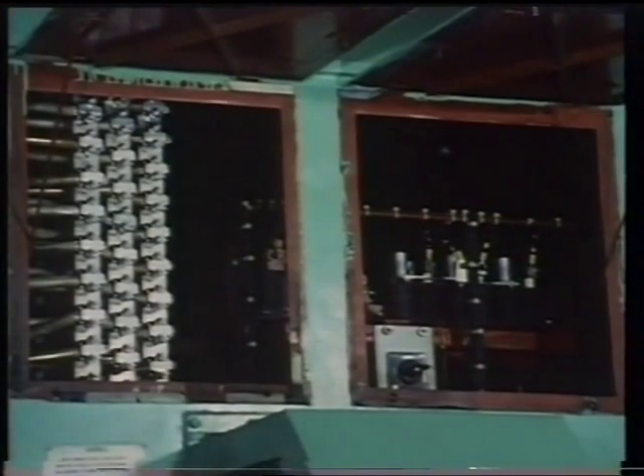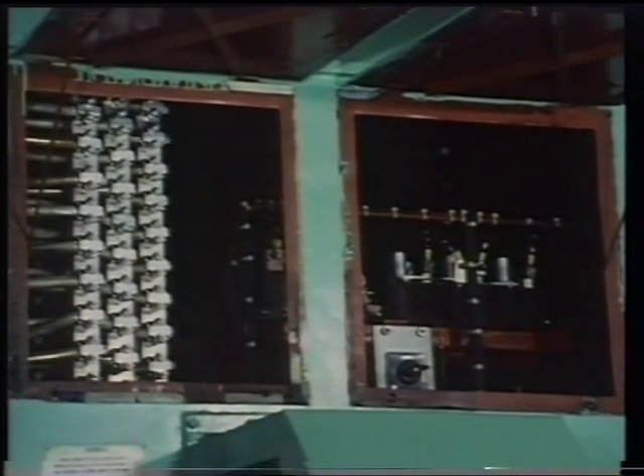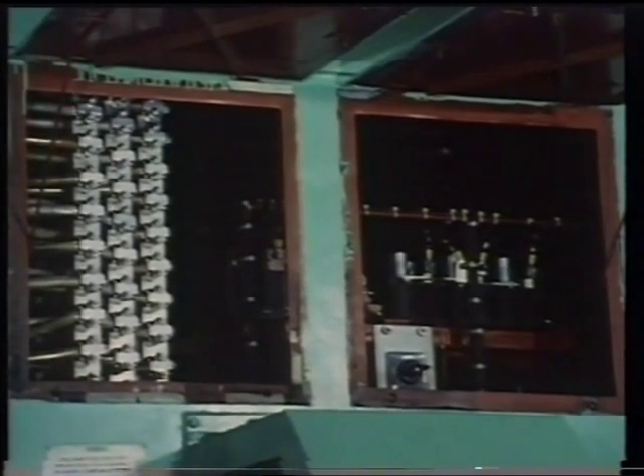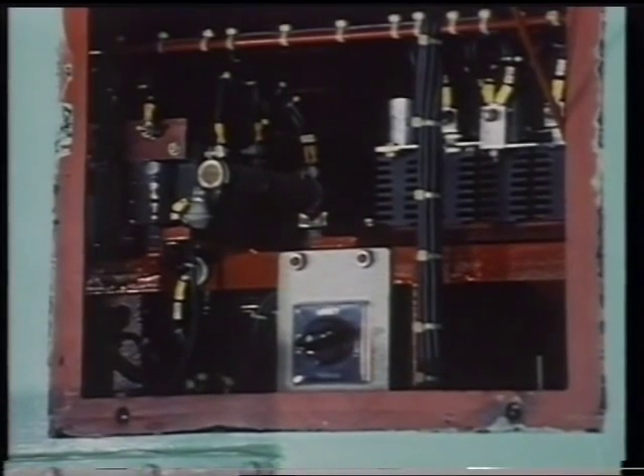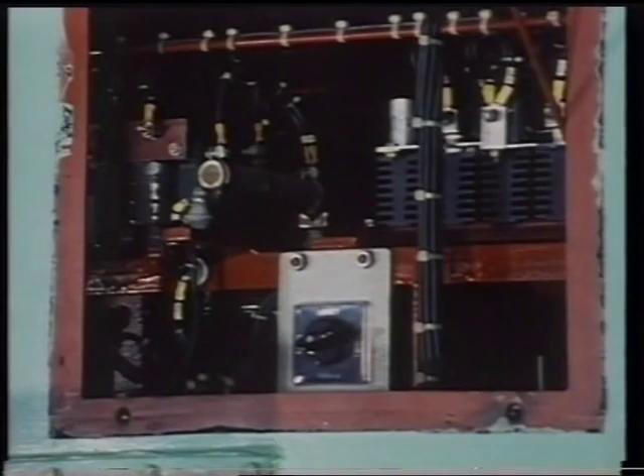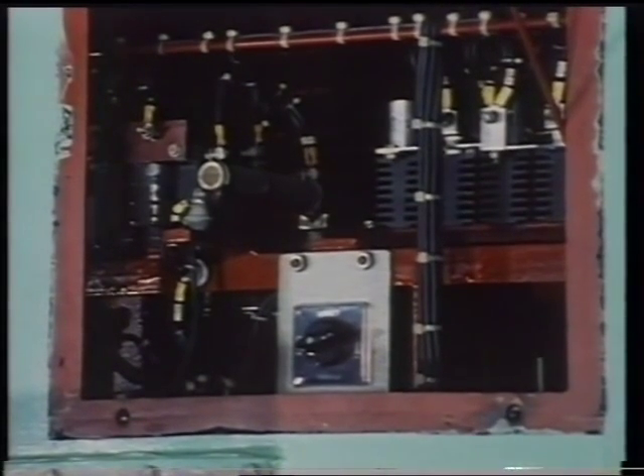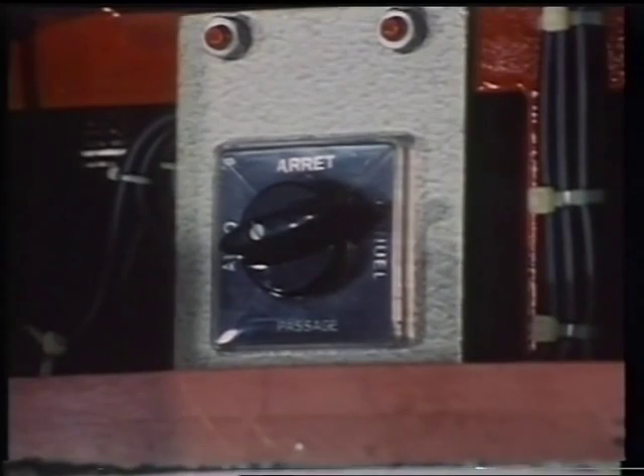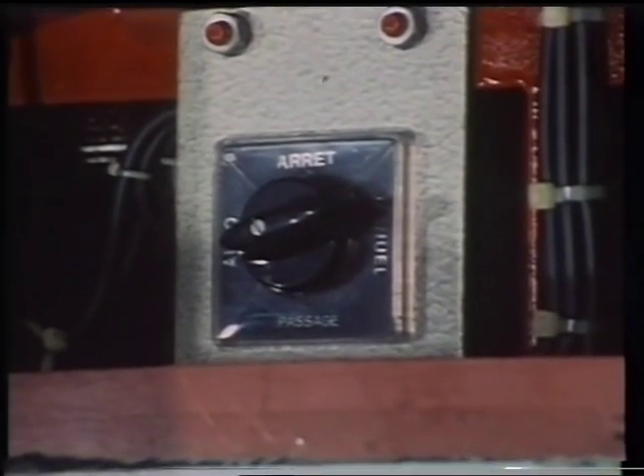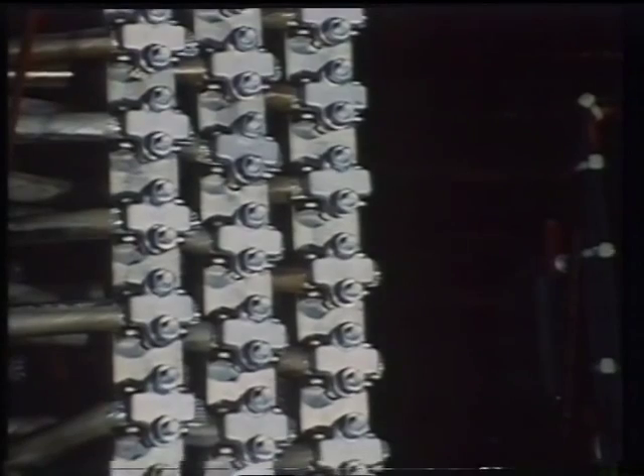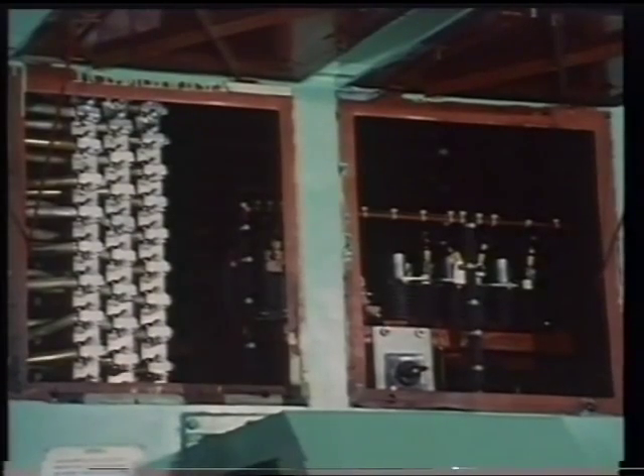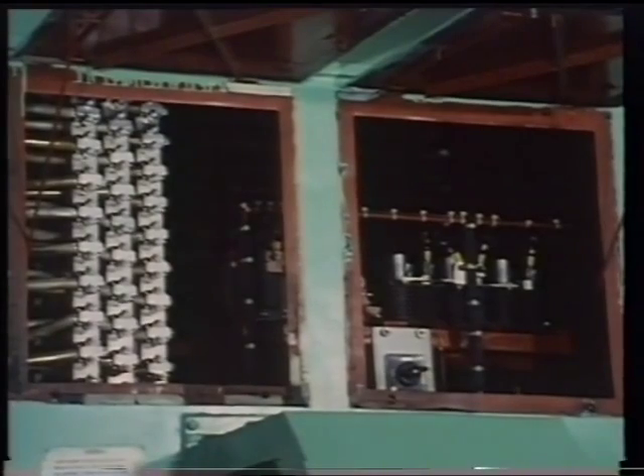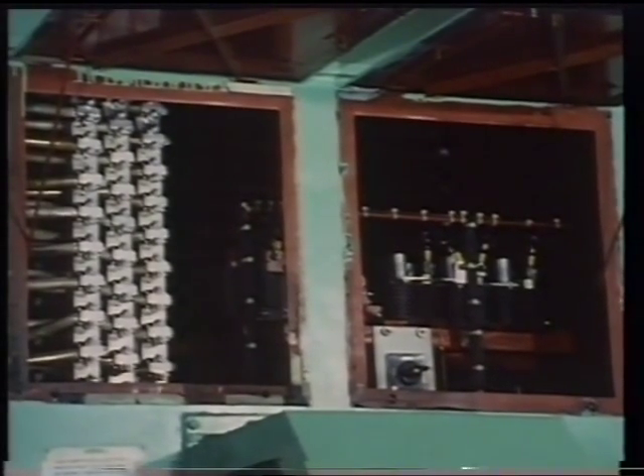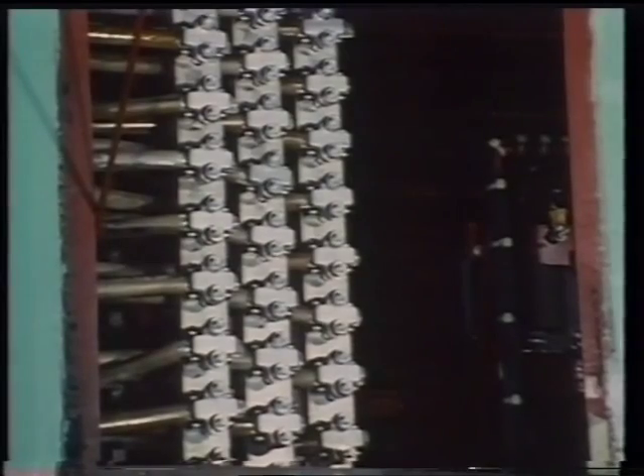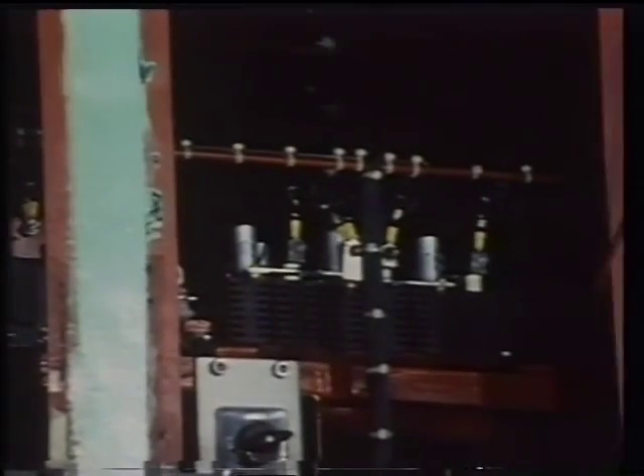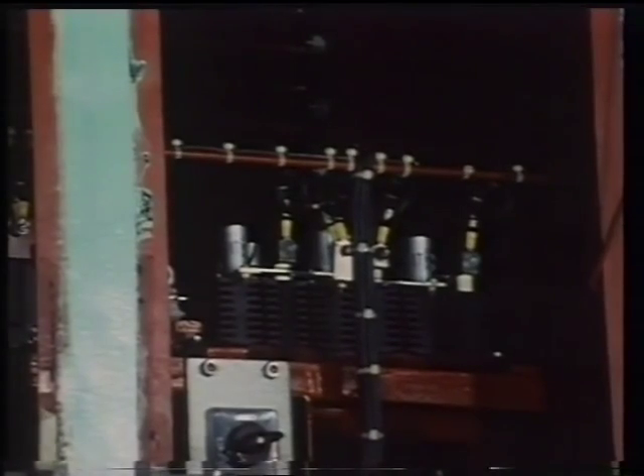The output voltage of the AC generator will be controlled by automatic voltage regulators in accordance with the changing power demands. AVRs are electronic devices which adjust the exciter current of the AC generators to maintain supply voltage at 440 volts as the various loads are added to or reduced. Voltage fluctuation without apparent reason is one of the symptoms of an AVR becoming faulty. If the voltage settles down on switching to manual voltage regulation, the automatic voltage regulator should be investigated and possibly replaced by a spare one.